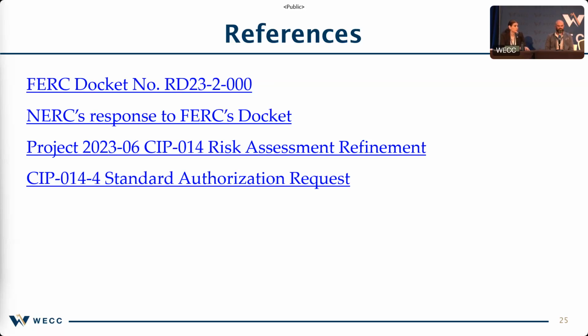How about some percentage of it? What is the realistic loss? The realistic loss is really going to depend on the studies done in the area, and this won't be determined through a CIP 14 risk assessment evaluation. It's probably going to be determined through the transmission planners or even the RC study, looking at that wider area, taking out different parts of the system and saying what's the largest amount of load I could sustain while guaranteeing I'll stay stable and not see uncontrolled separation. So it's a number that might vary depending on season, it may not even be a single value. You might choose the lower or higher of those two, depending on your own analysis and rationale.